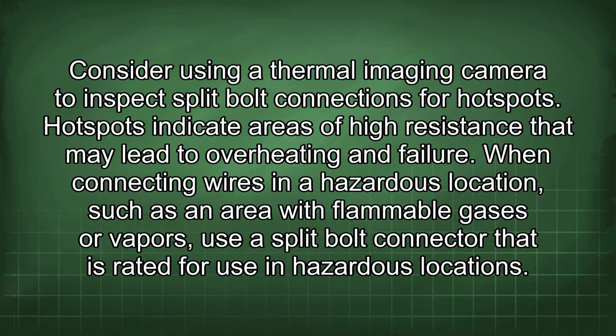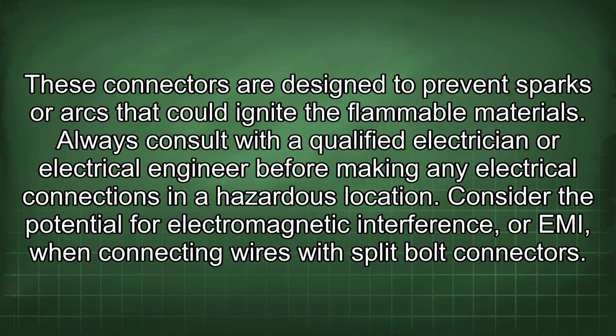When connecting wires in a hazardous location, such as an area with flammable gases or vapors, use a split bolt connector that is rated for use in hazardous locations. These connectors are designed to prevent sparks or arcs that could ignite the flammable materials.